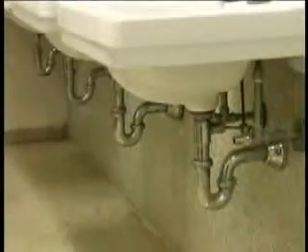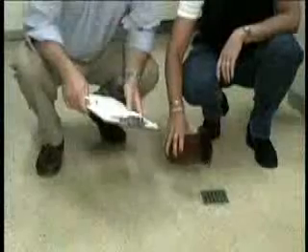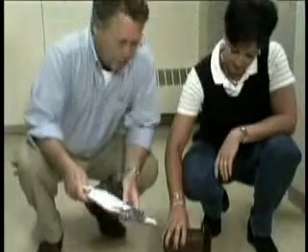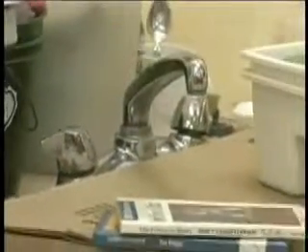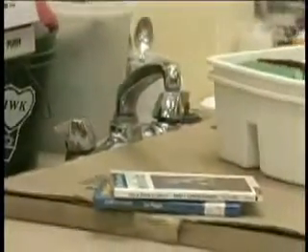Let's check the washrooms and general plumbing area and make sure that the exhaust fans are operating. Be sure that all drains have traps and are filled with water. These include ones in unused areas where they may be covered over for one reason or another. Drain traps can cause indoor air quality problems when the water in them evaporates due to infrequent use. If the building interior is under negative pressure, soil or sewer gas can be drawn indoors through a dry drain trap. Our next task is checking maintenance supplies.